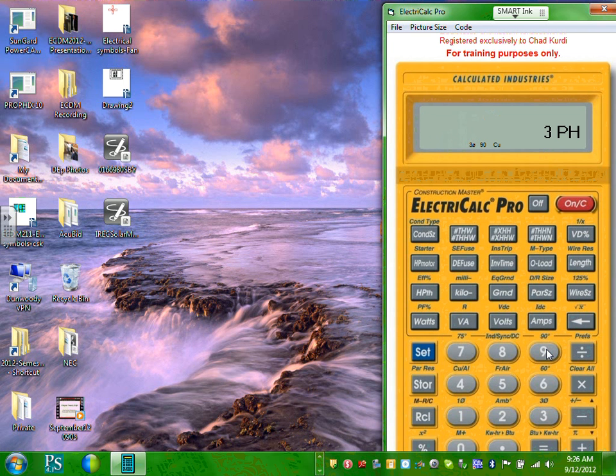So here's my warning for you. We're going to use this for commercial. When you do it for commercial, always make sure that your calculator is set for copper. So go back and set it for copper. Make sure it's set for 75. Set 75, and make sure it's set 3-phase. That's your default because you're using it for commercial, typically. I like this to be my default. Copper 75. That's my default. Cool. Everybody's okay with this? All right.